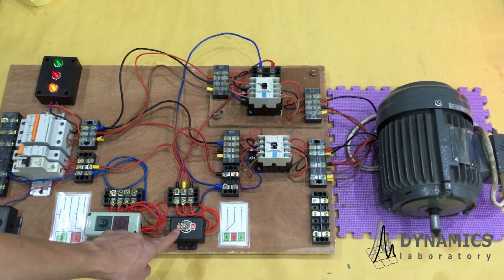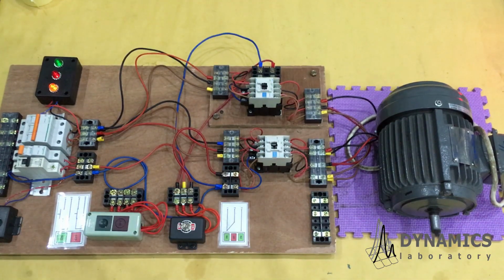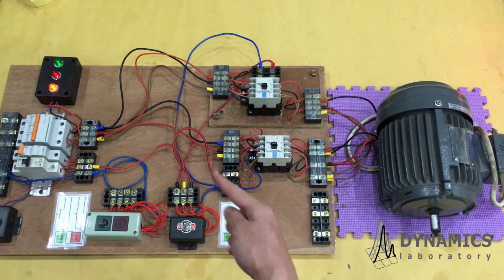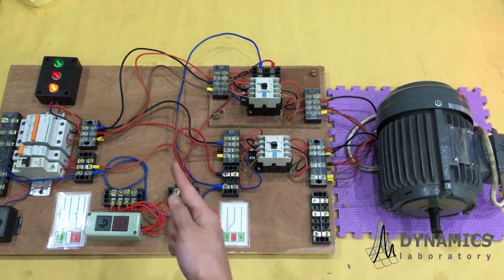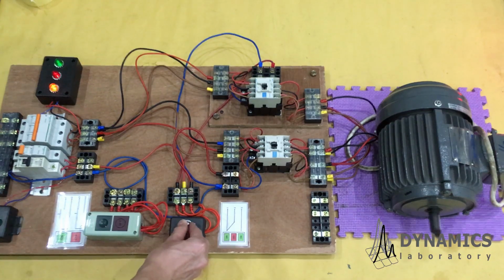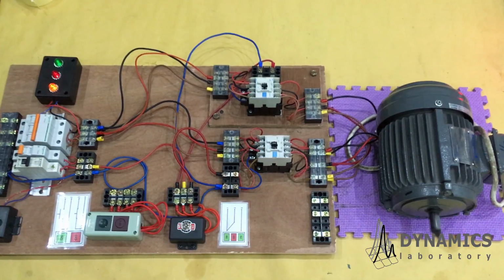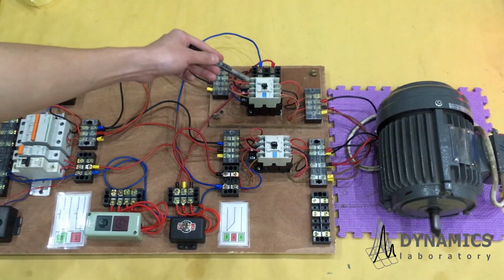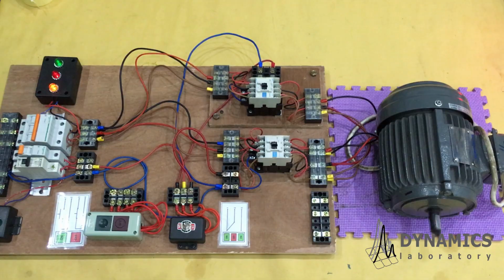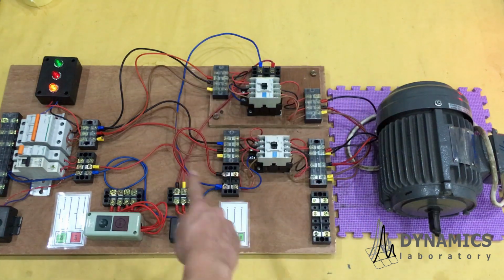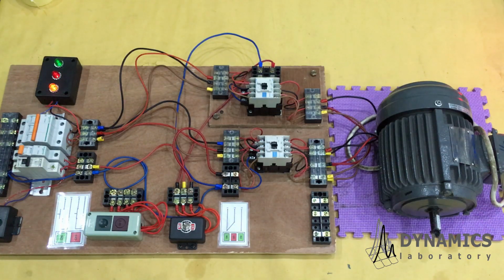Switch lever, the lever of the switch is in left position. That's why first contactor is turned on. The motor is already running, but we cannot see the rotational direction yet. That's why we have to turn it off, and we can see the rotational direction is clockwise. And for the second condition, lever of the switch is to the right. Second contactor turns on, and we have to stop it first to see the rotational direction of the three-phase AC motor. And you see, it's counterclockwise. So it's complete. We succeeded in reversing the rotational direction of three-phase AC induction motor.